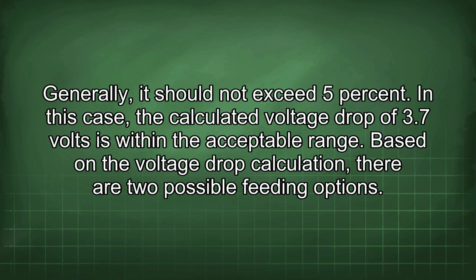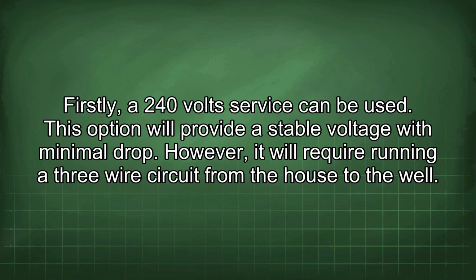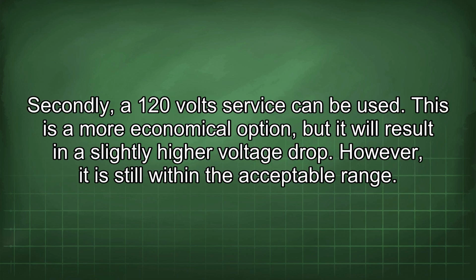Based on the voltage drop calculation, there are two possible feeding options. Firstly, a 240 volts service can be used. This option will provide a stable voltage with minimal drop. However, it will require running a 3-wire circuit from the house to the well. Secondly, a 120 volts service can be used. This is a more economical option, but it will result in a slightly higher voltage drop. However, it is still within the acceptable range.